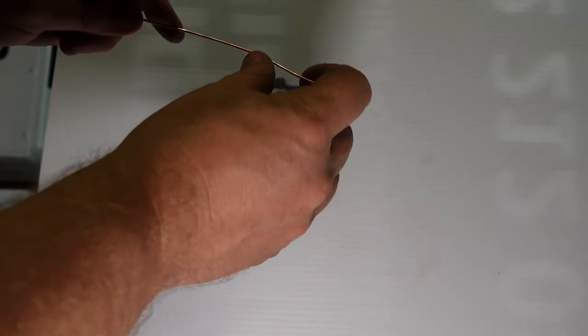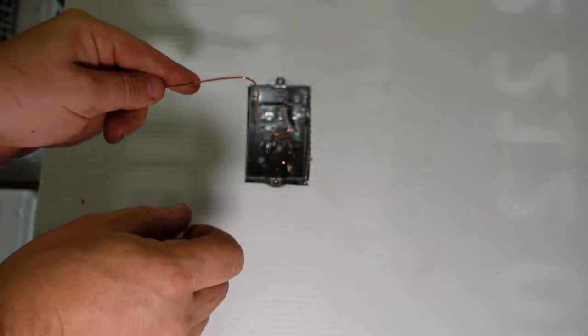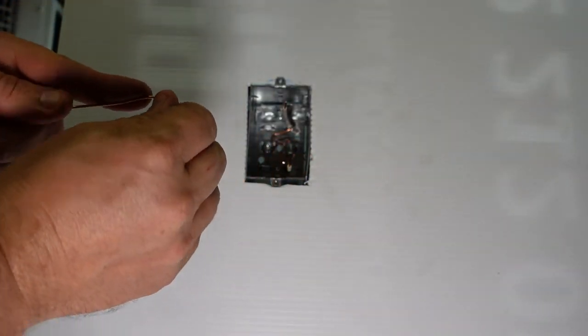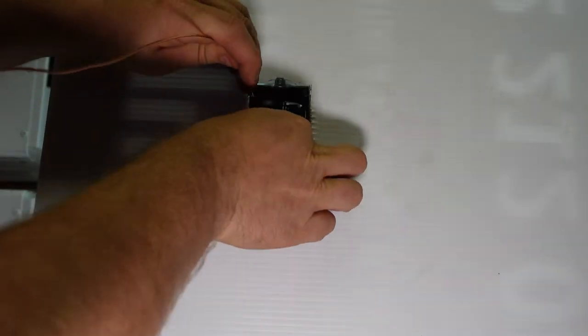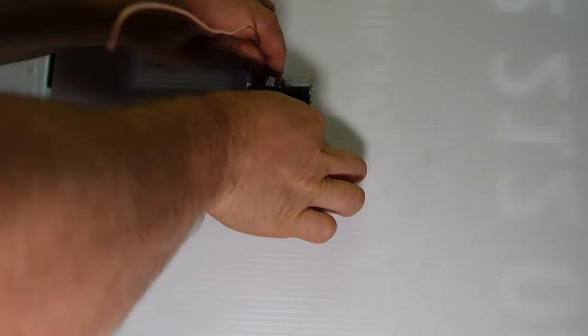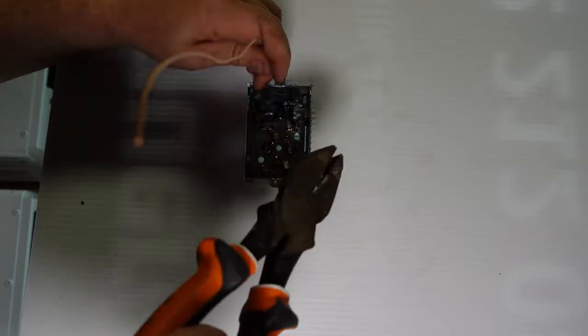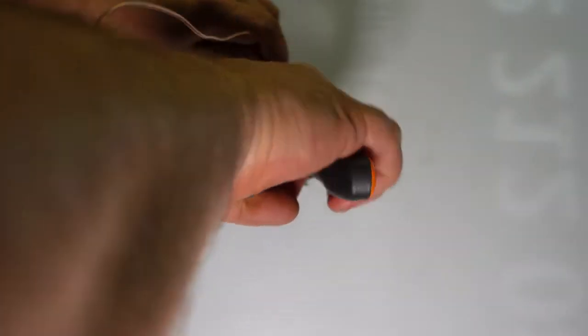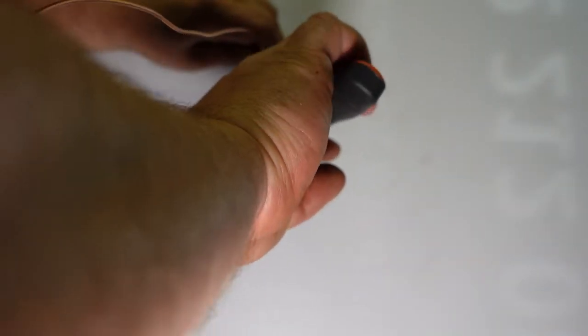So what we're going to do is we're going to take that wire and we're going to bend about two inches onto the back of it. Maybe a little bit less where those are a little bit shorter. And we're going to stick that in there and try to line them up with the rest of the conductors. Once we get them sort of into place where they need to be, we're going to take our linesman and we're going to twist in a clockwise motion. And that will secure them together and give us an extended ground.